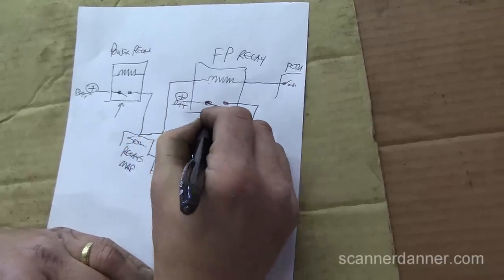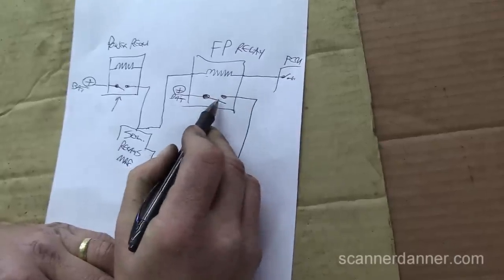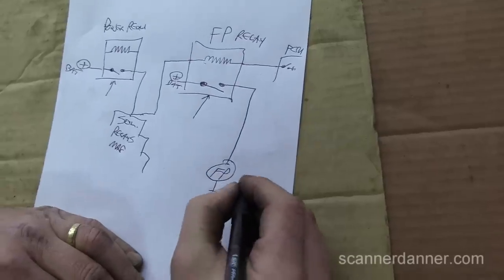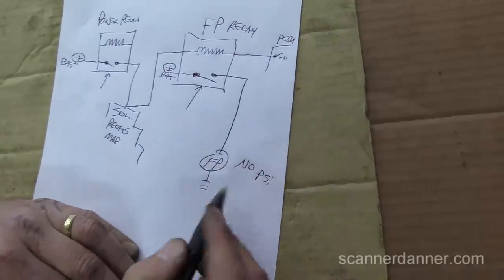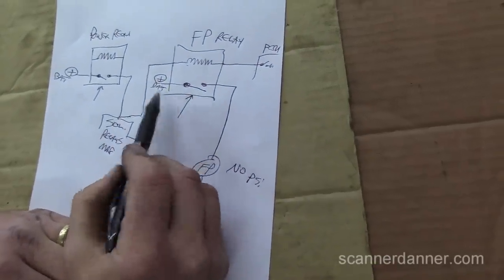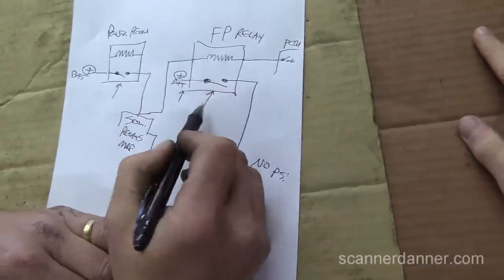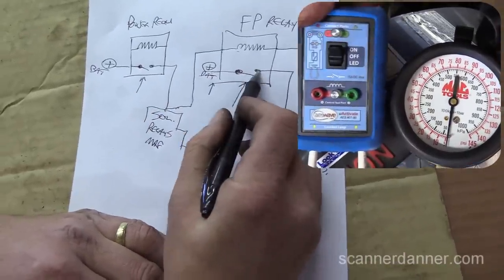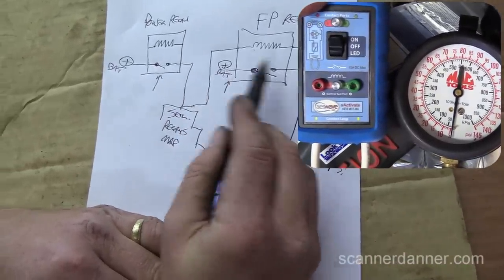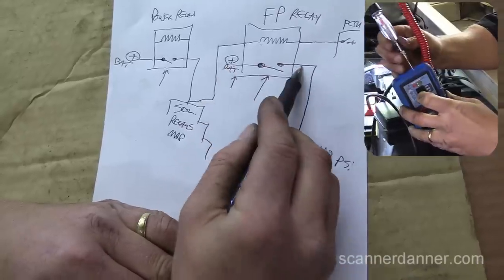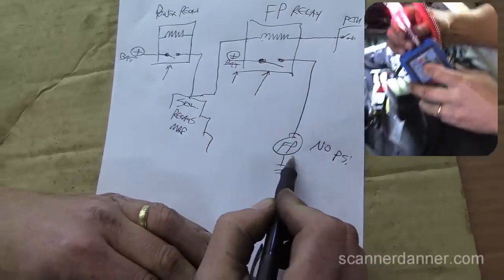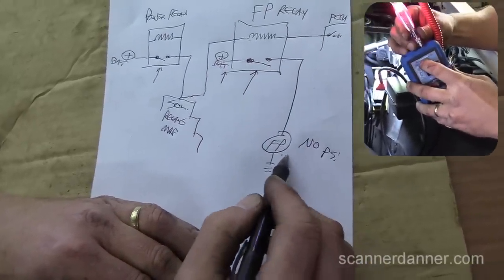And I did activate this, and my pump still did not produce pressure. We still had no pressure. So that's what I'm saying, we have two problems. Because if I'm energizing this manually with my uActivate tool, closing this, and I did confirm with my test light that I am sending power through, and the fact that our pump didn't produce pressure means we have a problem there.